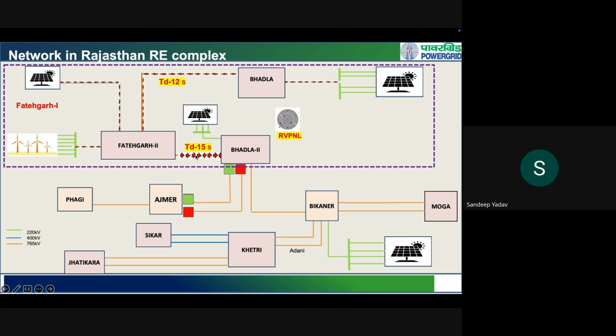So this is a very important link, and that is why the time delay for over voltage protection for this system should be much higher than the downstream transmission lines. The time delay for over voltage protection for these lines from Bhadla to Fatehgarh 2 is 12 seconds, and then there is a margin of 3 seconds for the more critical lines. So what happens if the transmission line from Fatehgarh 2 to Bhadla 2 trips? It will stop evacuating all the generation which is happening at Fatehgarh 2 and Bhadla.